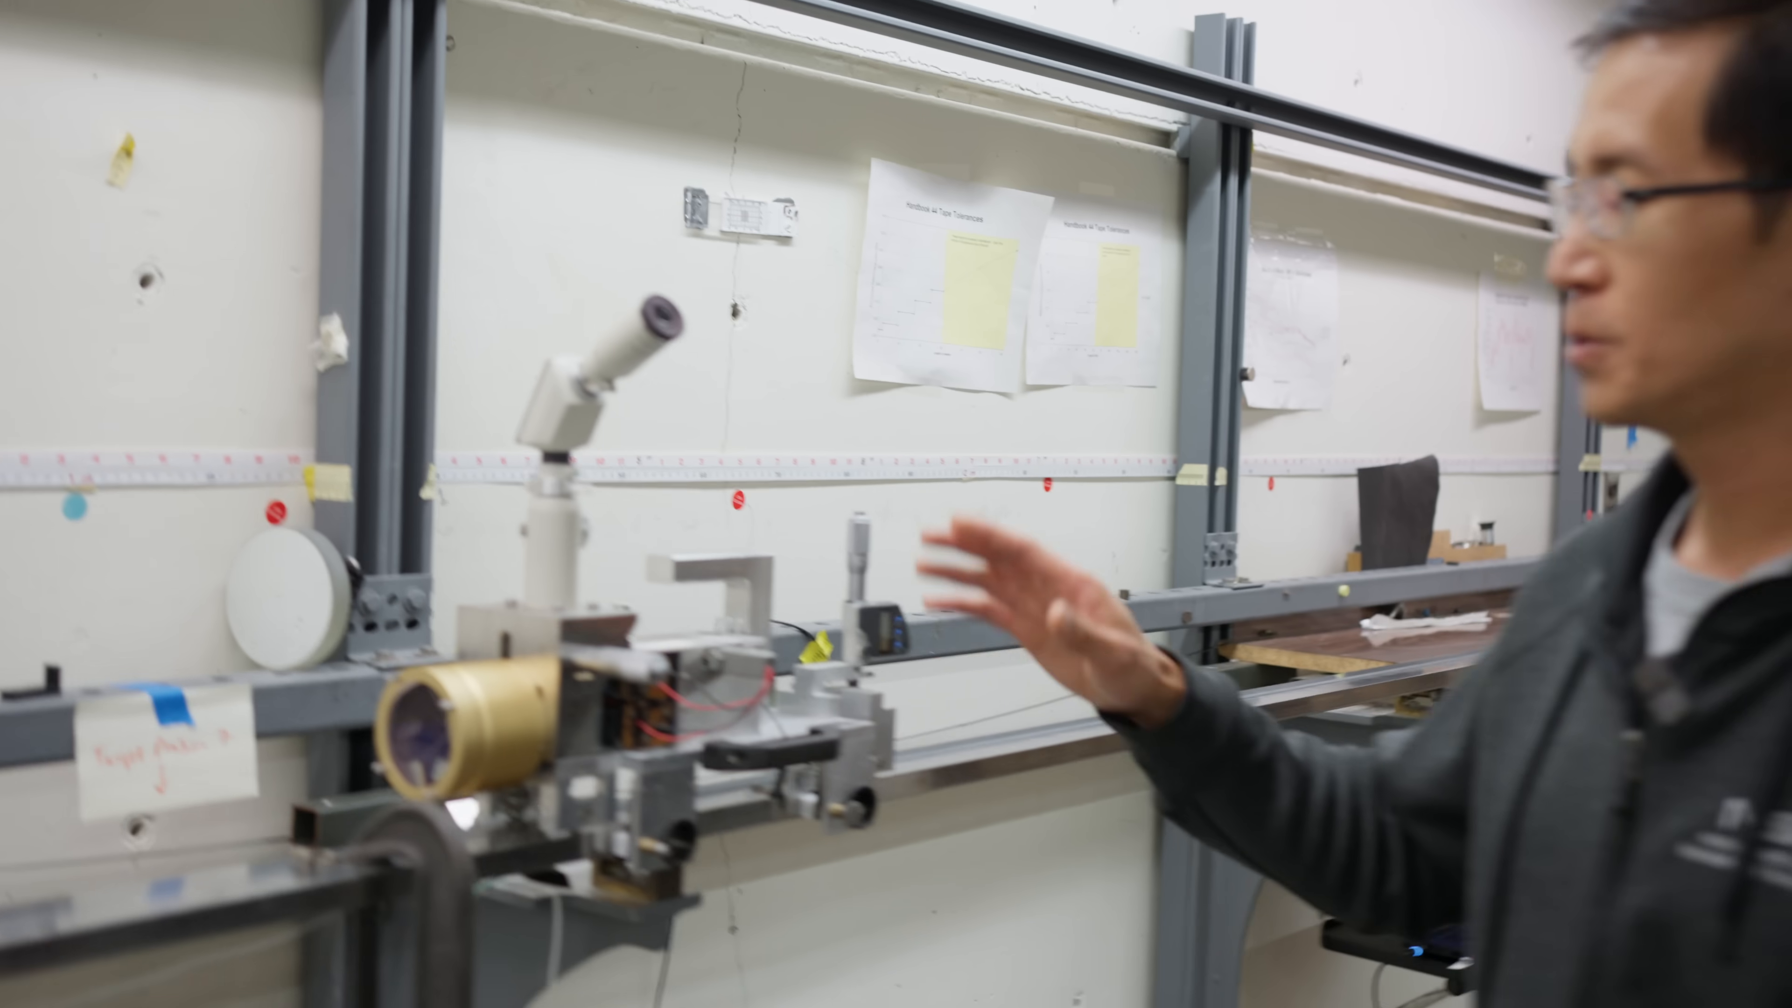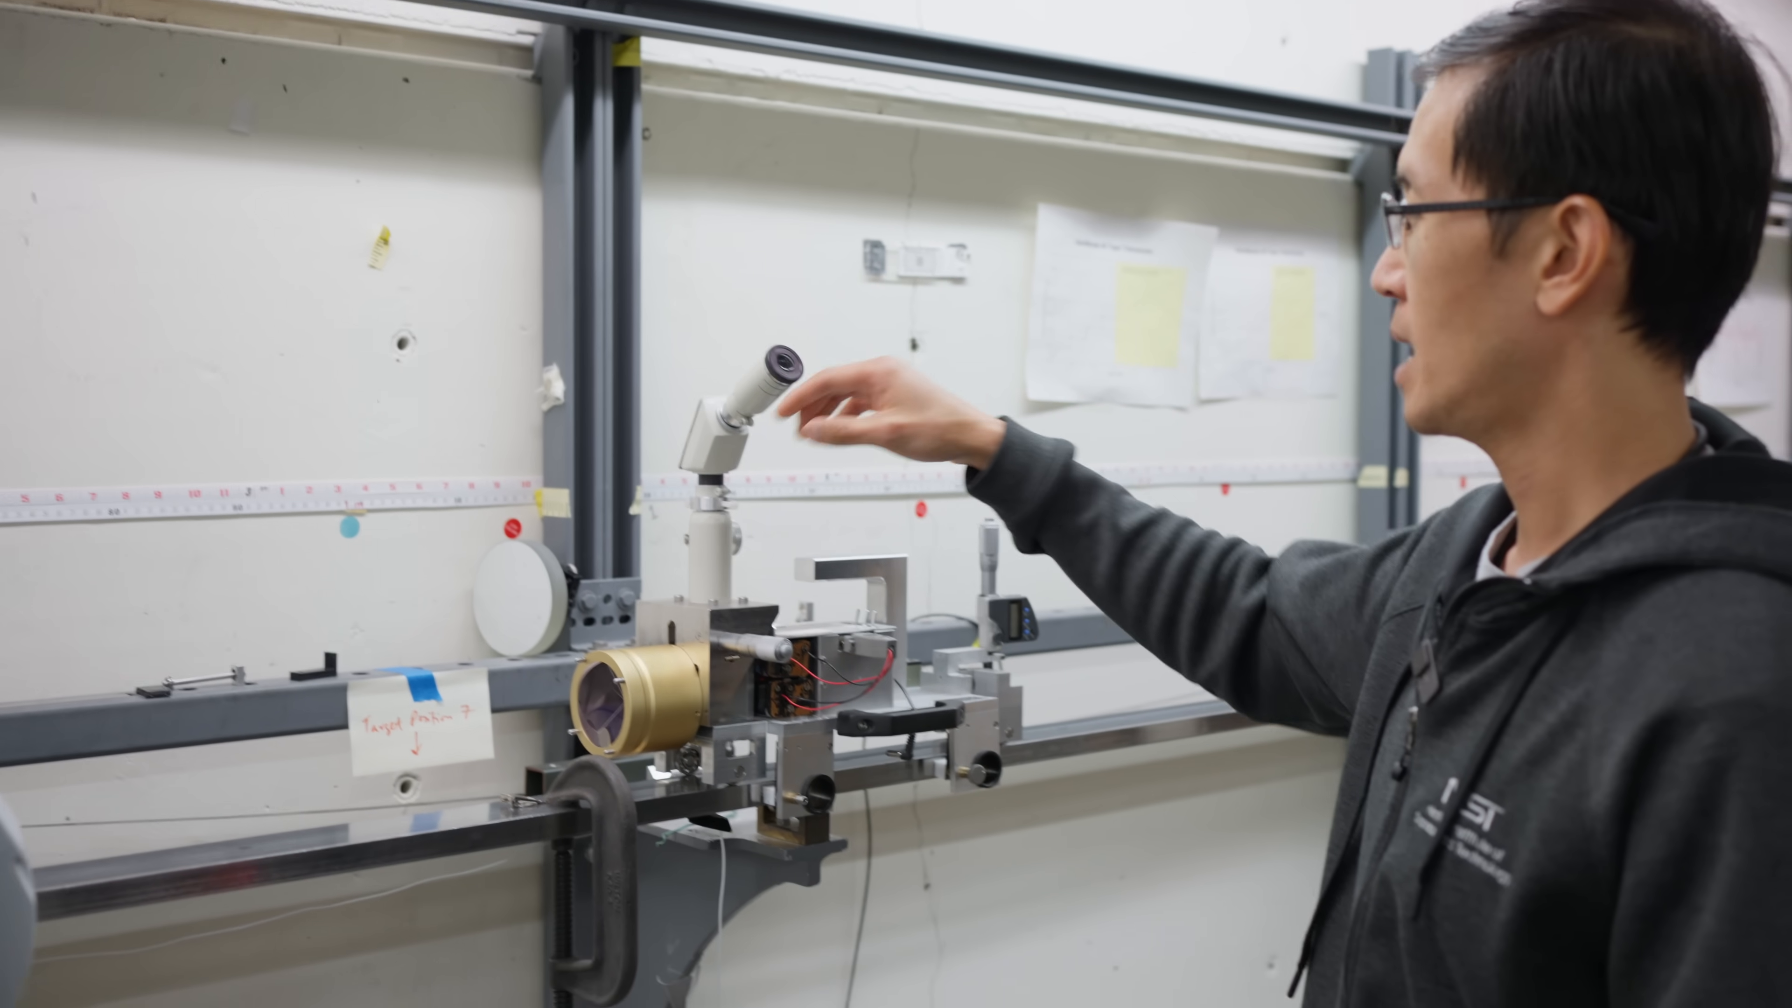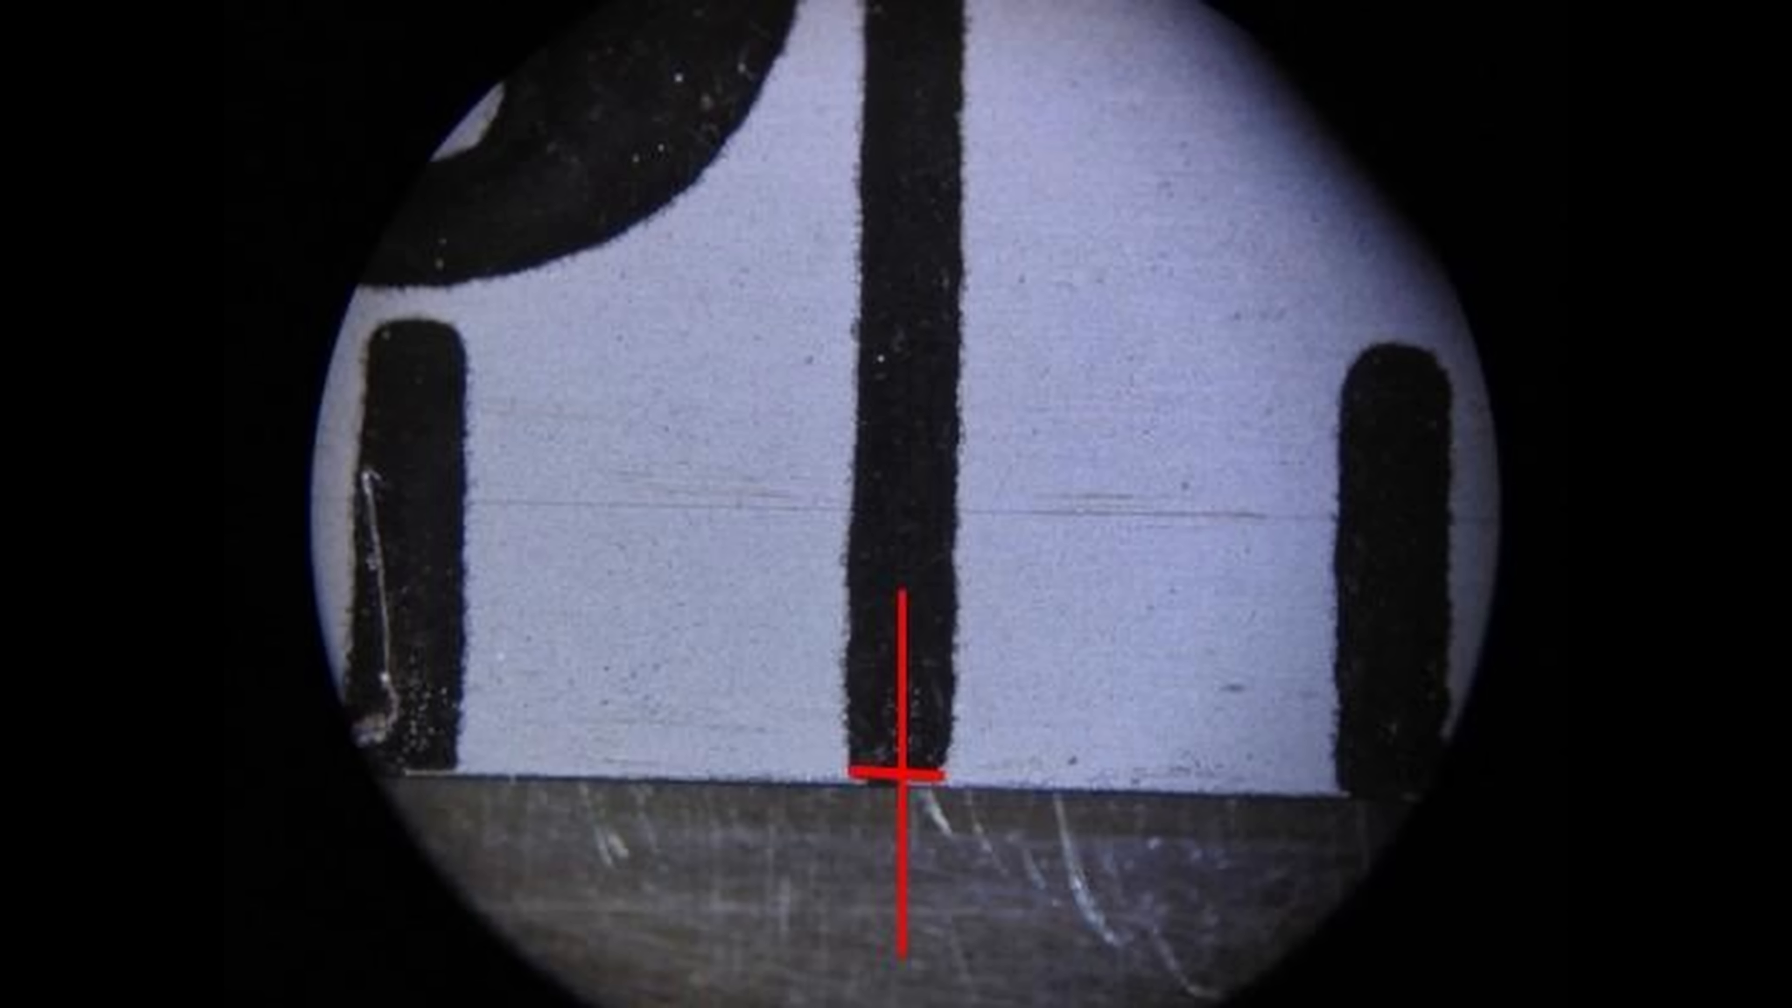So in order to tie in the reference laser measurement to the measurement tape, we have this tape carriage, which uses the retroreflector, which interfaces with the laser interferometer, and an optical microscope that has a set of crosshairs for you to look through and align to the hash mark that you want to measure. So right now, I have it aligned to the zero mark of the tape.